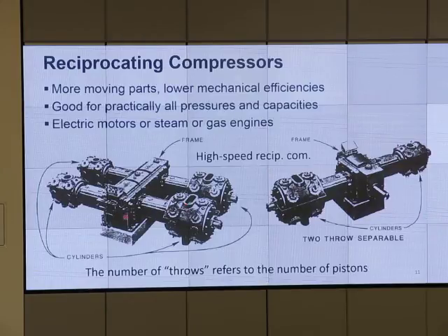So you compress high volume gas to lower volume gas, and then this mass goes to the second stage and you compress it again, and then it moves on. So you have continuous mass flow, but the volume just keeps going down. So when you do it in practice, the first stage has a larger chamber than the second stage. The second stage has a smaller chamber.